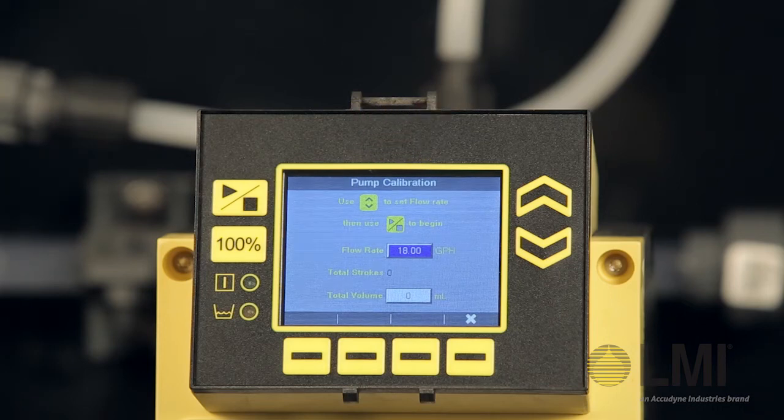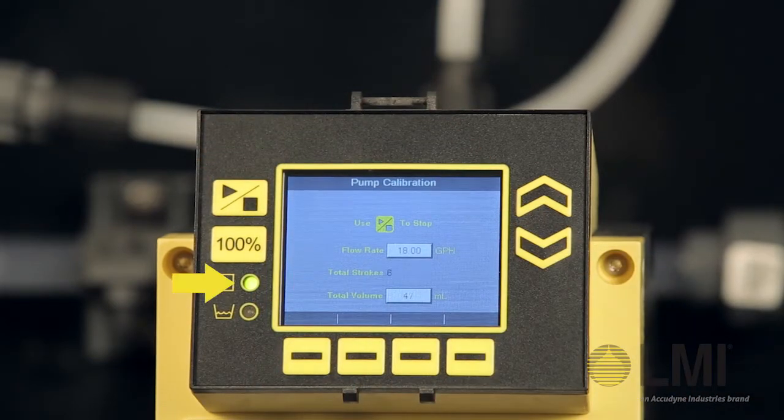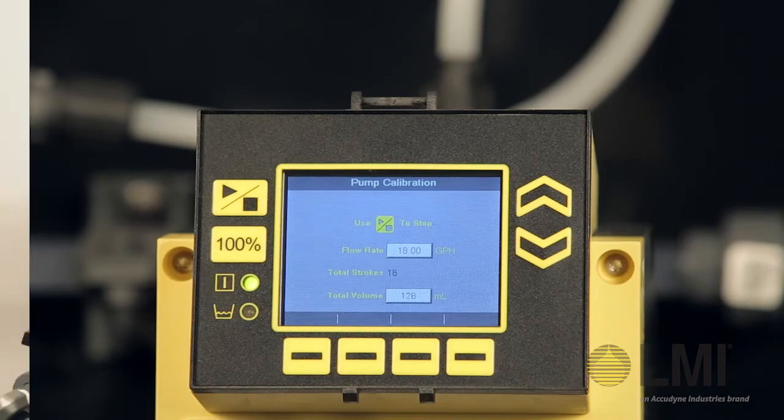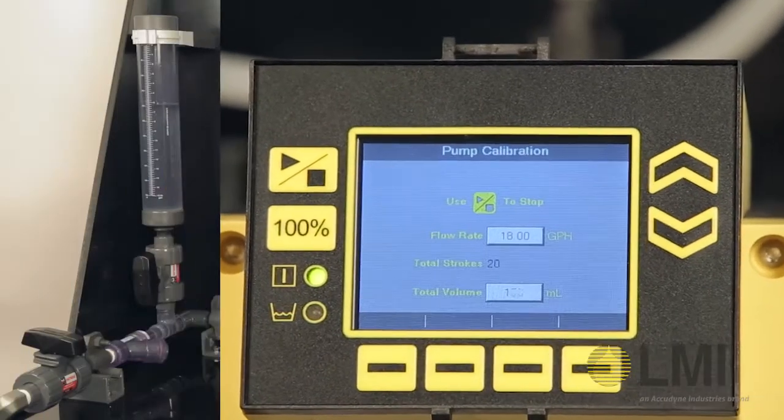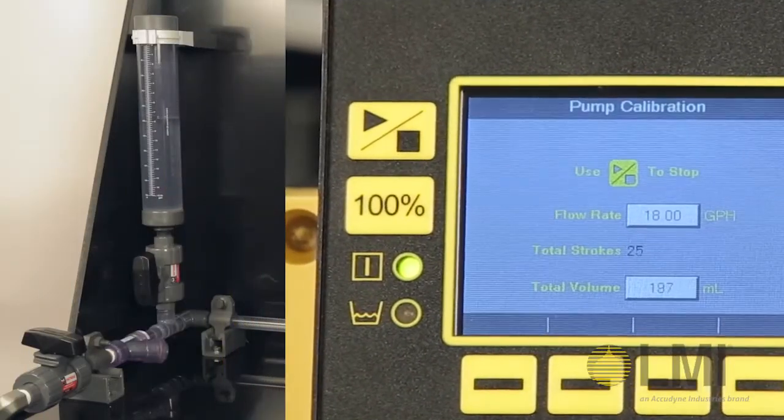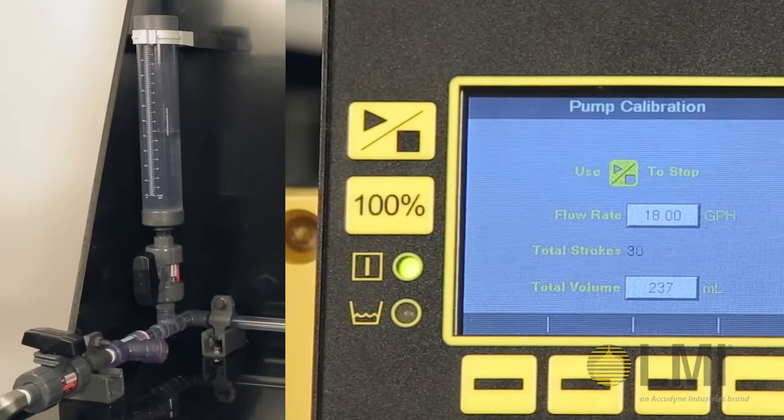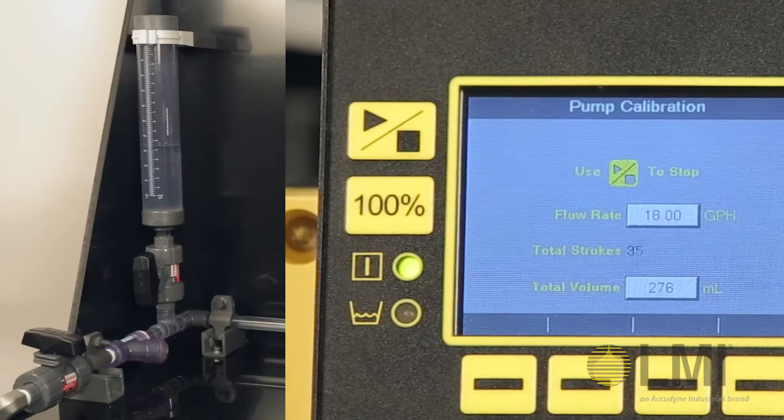Press the Start-Stop button on the left side of the display to start the pump. The green LED power light will illuminate to show the pump is now operating. While the pump is pumping, the stroke count and total volume on your display will increase, and fluid will begin to empty from the calibration cylinder.